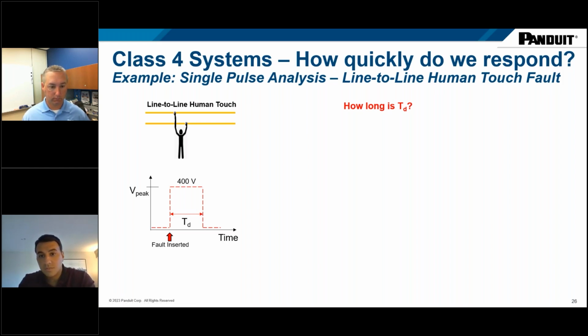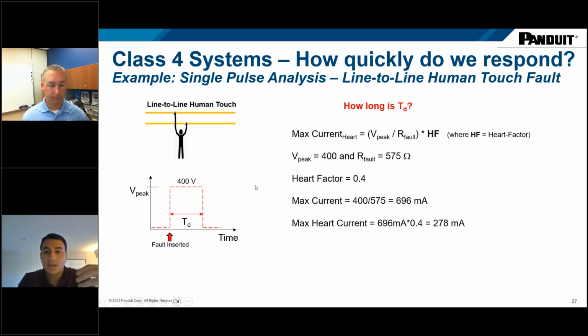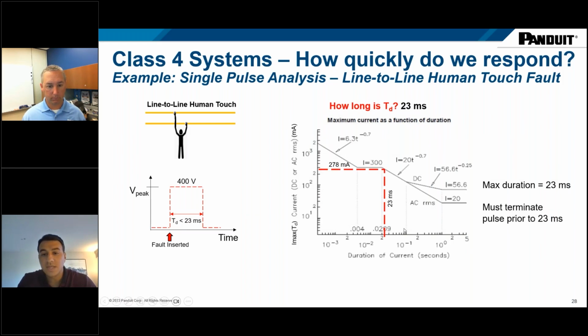And so if you go through the calculations based on the voltage and based on what's called the heart factor, which basically is defined as how much current is going to flow through a person's heart if they touch the two copper conductors, you get to what's called the maximum heart current. And then you can use this value to go back to that curve and say, okay, I have this much current, how long can that pulse last? And in this case, it's 23 milliseconds. So if you design a system that's just a single pulse and you want to adhere to the standard requirements for line-to-line human touch, you need to turn off that power at 23 milliseconds or before it.